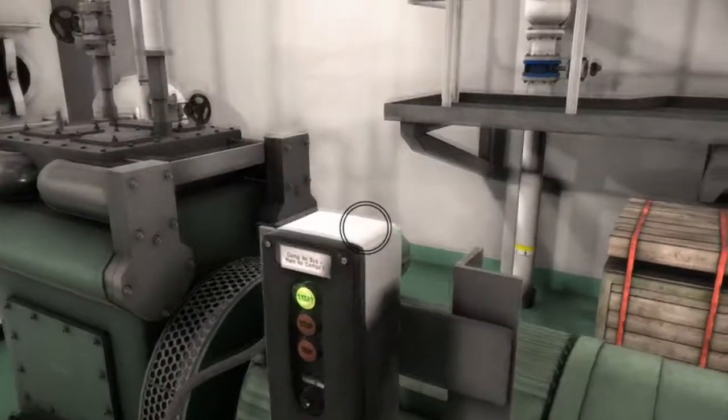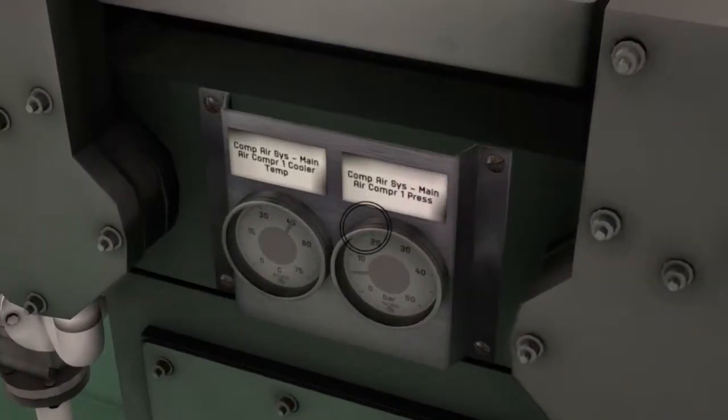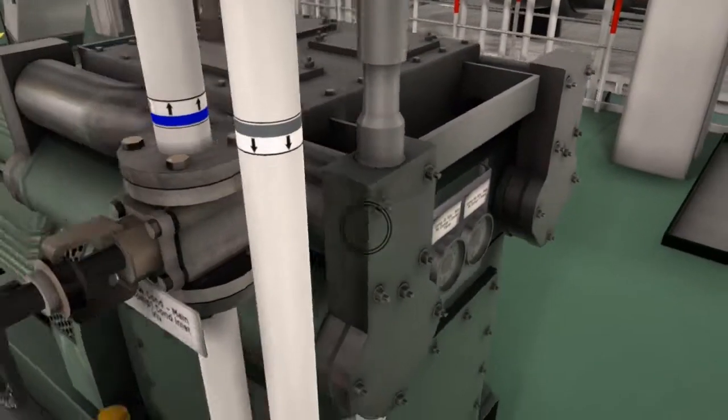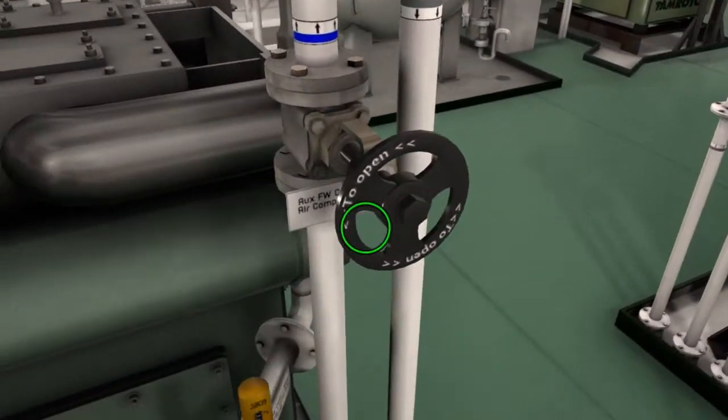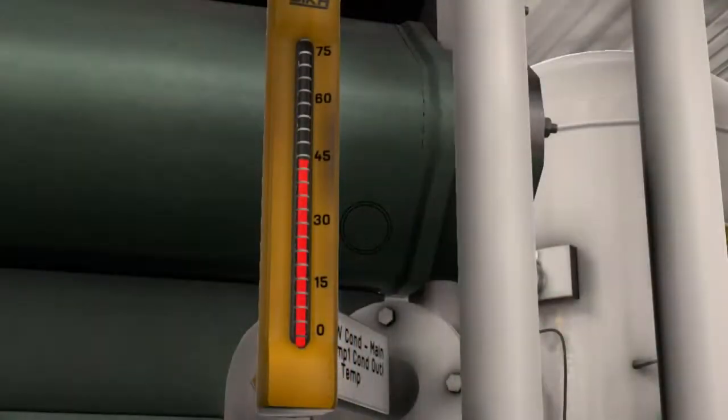Now check the pressure and temperature deviations of the compressor. If any abnormalities are found, rectify it immediately. Then check the cooling water temperatures of the compressor to ensure that it is below 60 degrees Celsius.